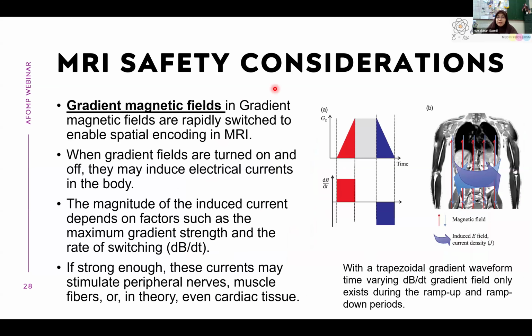And then we have the third one, which is the gradient magnetic fields. Gradient magnetic fields rapidly switch on and off during the procedure to enable the spatial encoding in MRI. That's how we create the gradient magnetic fields. When you do the turning on and off, they induce electrical currents in the body. This follows Faraday's law. The magnitude of the induced current depends on factors such as the maximum strength and the rate of the switching. If it's strong enough, it will generate currents, and it may stimulate the peripheral nerves, muscle fibers, or in theory, even the cardiac tissues. So this is something that we also need to be aware of.